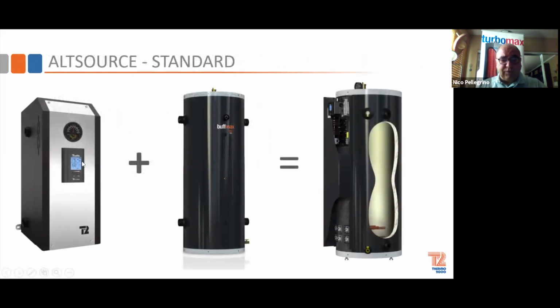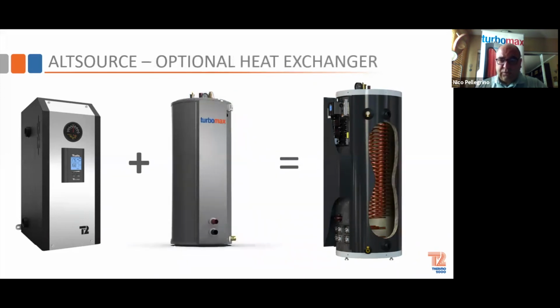So basically all we did was we took an electric boiler with our Buffmax, and it became the alt source, with a standard boiler tank style boiler with heating elements. Then what we did was we also took an option of the copper coils inside of it with the Turbomax, so if you're marrying it with a boiler that can give you high temperature to make domestic water, then you don't need a finishing tank or an alternative tank for the domestic. Or you can do it as a preheat, so your COP on your alternative energy is a lot higher, so your delta T is reduced in to the finishing tank.